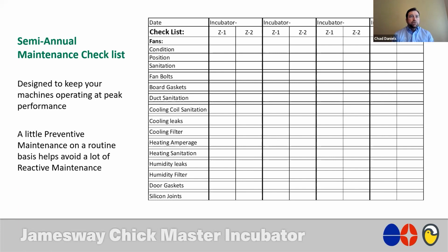And then for the top portion of this, we finish up with looking at door gaskets and then also silicone joints. I think everybody probably understands the door gasket review or comment and the reason it needs to be checked, but we oftentimes overlook silicone joints. And what my reference to that is the way the machine is physically put together. It's constructed of fiberglass reinforced panels, or FRP, and they're joined together generally with an aluminum extruded material, and then it's riveted, and then those joints are siliconed. And what can unfortunately happen over time is the silicone can get washed out or pressure washed out of that seam, and then you create an opportunity to allow moisture and bacteria to get down into that joint. And then you have a bacteria source that's almost impossible to ever get cleaned out. So it is critical to check that periodically.